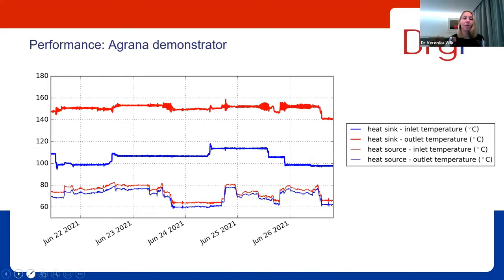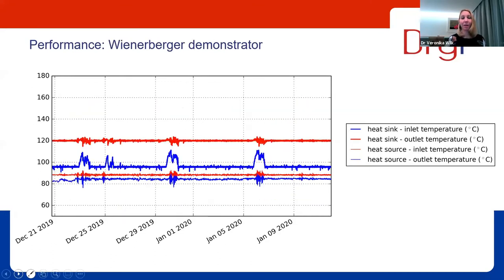So this is another week of operation. In June this year, we see again fluctuations in the temperature of the heat source. And in this time series, we also see that we have changed the condition of operation of the heat pump. So we have tested different temperatures. So this is operation at higher temperatures. It's 150, 155, what we have tested here. So these results were also very satisfactory, well functioning of the process control, and also high heat supply temperatures. This is a similar illustration for the Wienerberger demonstrator.